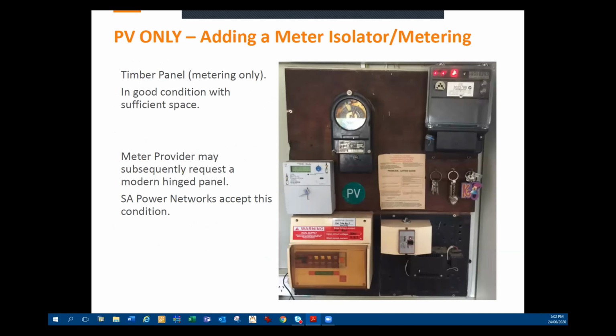So we've got some examples, such as PV, adding a meter isolator and metering. So timber panel, metering only. If it's in good condition with sufficient space, which this one has, then there's no requirement under SA Power Networks to change that meter panel. But a meter provider may subsequently request that a modern hinged panel is installed, and SA Power Networks accepts this condition. Because for a meter provider to make their life easier, they don't want to have a board that they're trying to hang off and putting stress on cables, and a lot of other issues with the larger boards or some of the boards that are out there. So if a meter provider does require that it's hinged, then that just becomes their requirement then.